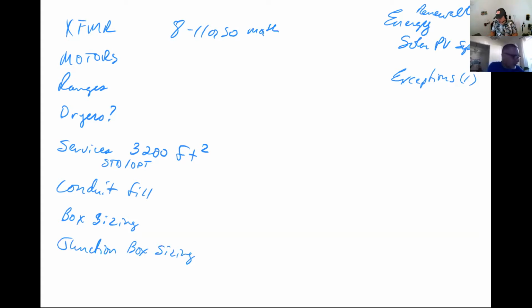I want you to note that C note 1, just put to the right of that, draw an up arrow, because that means you're going to be allowed to round up because of that note 1. If you don't have that note 1, you can't round up. So the 250% on the second row would be rounded down, if you follow my drift.